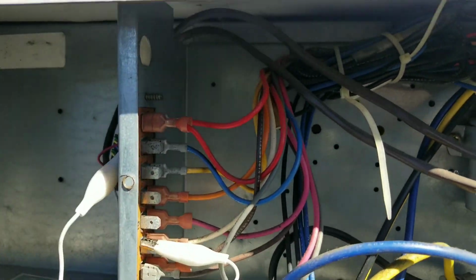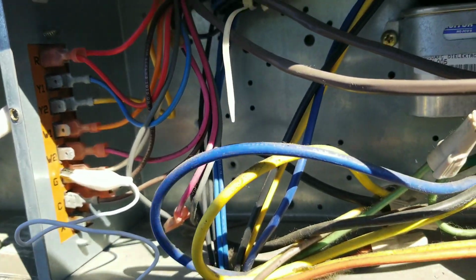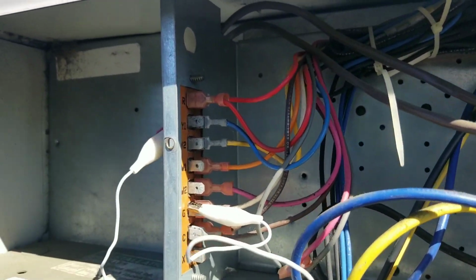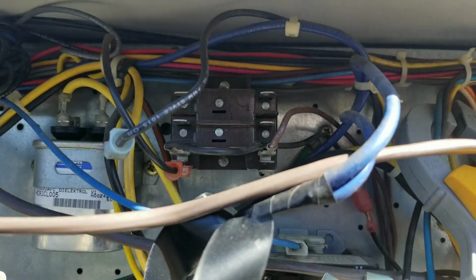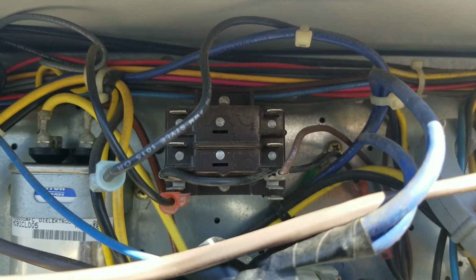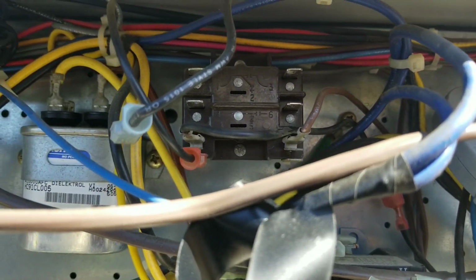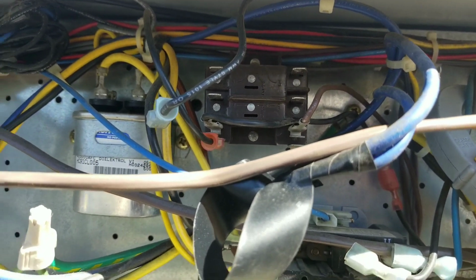For now, I have my call for cooling disconnected. I just have a bypass jumper on my indoor blower motor. So we're gonna fire it up and see if I have continuity across that switching relay. I should. I don't think I do though.